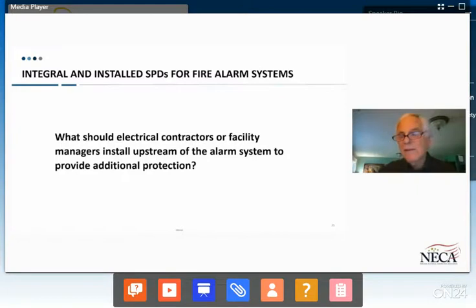Well, our view is that the SPD that we provide at the panel level is kind of like the last level of protection. It's the last hope, and there should be robust protection installed at the service entrance, either Type 1 or Type 2 protection. And then if there's a distribution panel or more than one distribution panel between the service entrance and our control panel, we'd like to see an SPD provided at each additional level of distribution, and then of course finally the SPD that we've talked about before provided at the load, so that there's a network or a tiered approach to protecting from these surges, because we know that any surge protective device in the system is not 100% effective.